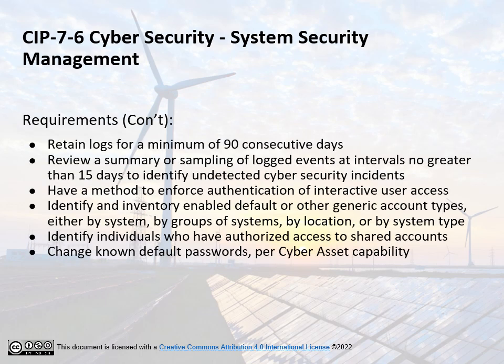CIP-007-6 System Security Management. Requirements continued. Retain logs for a minimum of 90 consecutive days. Review a summary or sampling of logged events at intervals no greater than 15 days to identify undetected cybersecurity incidents. Have a method to enforce authentication of interactive user access. Identify and inventory enabled default or other generic account types, either by system, by groups of systems, by location, or by system type. Identify individuals who have authorized access to shared accounts. Change known default passwords per cyber asset capability.